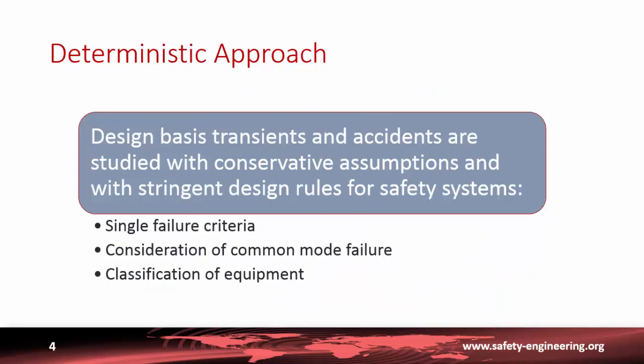These design transients and accidents are studied with very conservative assumptions. All initial parameters are taken at the worst condition, and very stringent design rules for the safety systems are used, such as the single failure criteria, which assumes that any failure could occur on the safety system reducing its capacity to counteract accidents. Also in this kind of study, consideration is taken for common mode failures.